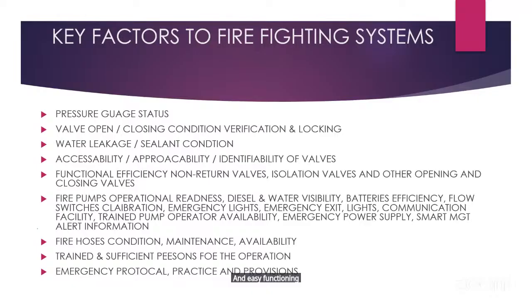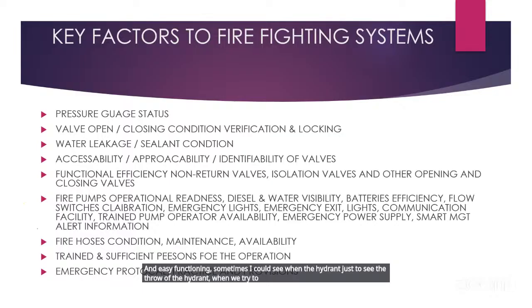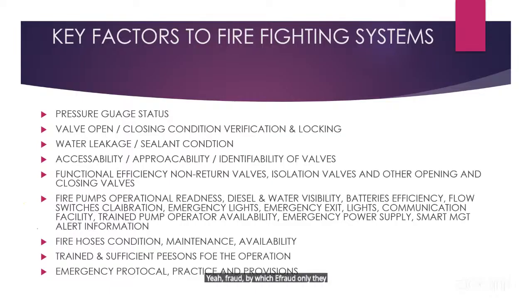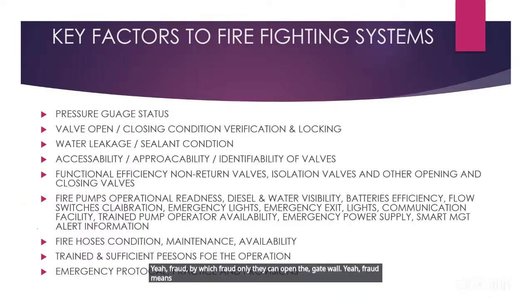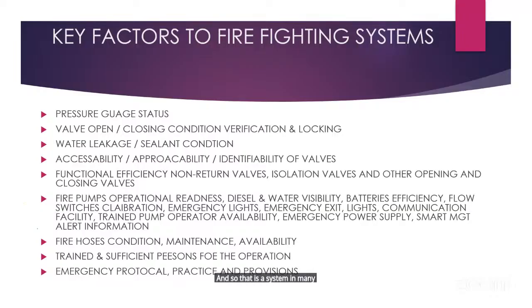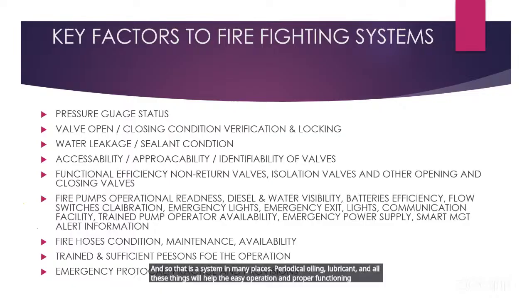Isolation valves and other opening and closing valves must always be tested for proper, efficient and easy functioning. Sometimes, when we try to see the throw of the hydrant by putting hoses, we ask the person to open the valve. They try like anything but cannot open it. Then you use an F-rod, with which they can open the gate valve. F-rod means fail rod, because they fail to open it by hand. In many places, periodic oiling and lubrication help easy operation and proper functioning of valves. The water should also be kept in good condition as much as possible, so that rusting of the valves and system is less.